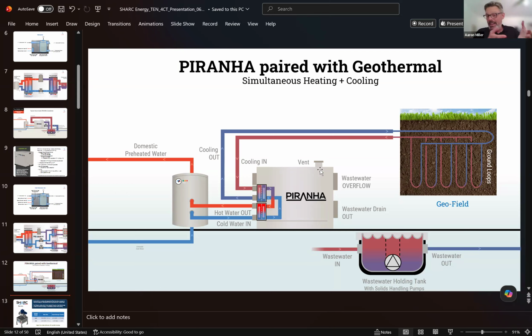Don't use it for your school right now directly. Shove it into the ground loop to bring that loop up to temperature so that all the other water-based assets, again, connected to that loop, are operating at capacity and efficiency. And then once that loop tempers and hits the right temperature, a three-way valve switches, and then you store the rest of that hot water for the school. And the system just toggles between tempering the ground loop and making hot water for the school. So again, there's an application where we're using potable water for a non-potable application.